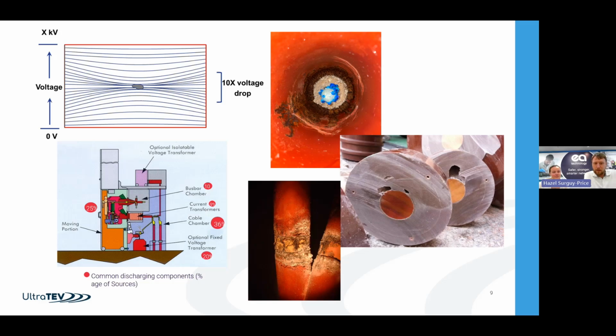You might start to wonder whereabouts in the switchgear this might occur. That's the kind of case in the bottom left-hand side there. And it's certainly a fact of life that we cause a lot of these issues. When we're in there doing maintenance, or anywhere that we've done installation on site, cable terminations or moving parts, they're the parts at higher risk. But they're not the only parts. There are common failure modes in different types of switchgear, design flaws, or even just impurities in the air, humidity, etc., that can cause breakdown across the surface of busbar sections and the fixed portions. So there is a higher risk in the bits we interact with, but it could obviously occur anywhere within the switchgear. So that's just a flavour of what PD is, and you can see some of the effects there.